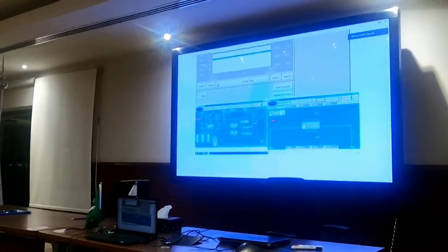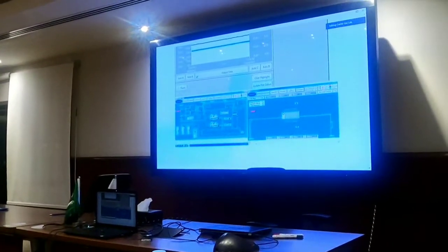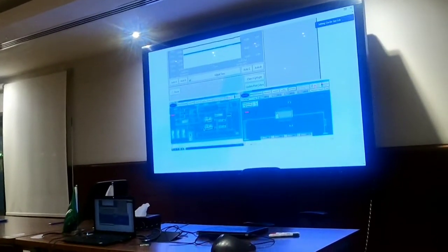This control screen that you see here is pretty much what he monitors. He'll go back and forth. If he needs to change boiler temperatures to get more temperature on the chiller, he can go in and manipulate and change the temperature. He can also go in here and open and close pneumatic valves slightly to change the temperatures. This is pretty much all automated. He goes into the little block that will appear on the screen, he makes the changes, the computer will go ahead and open and close slightly the valves that need to be, and that temperature takes place.